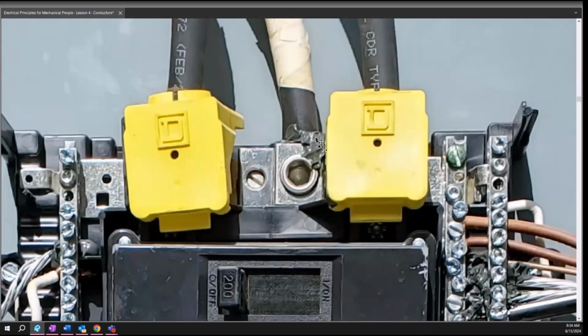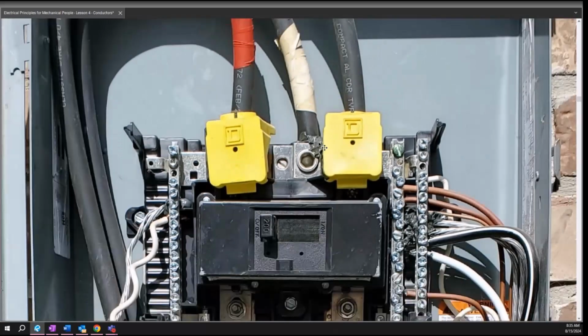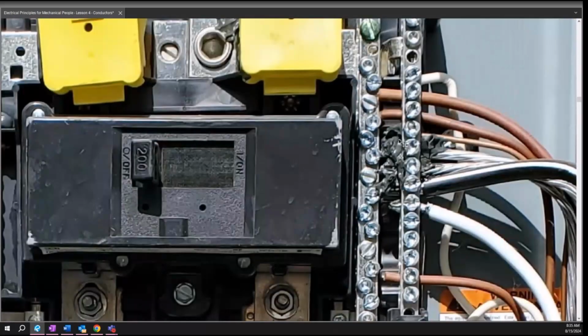If you look real close, you can see this big, huge goop of stuff. This is called Noalox. It's a name brand, but all it is essentially is an antioxidant, so that the aluminum doesn't start oxidizing, not allowing ampacity to flow through it. You know how metal rusts? Well, aluminum doesn't rust. It actually oxidizes. It forms a very thin layer, we'll call it rust, on the surface, and that inhibits more of it from rusting. That's why aluminum, quote unquote, doesn't rust. It protects itself pretty much.